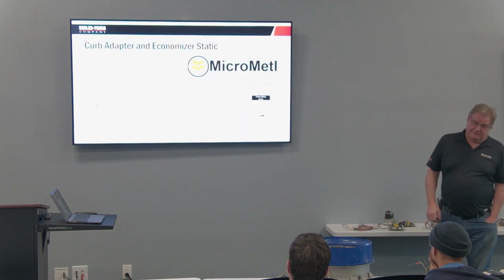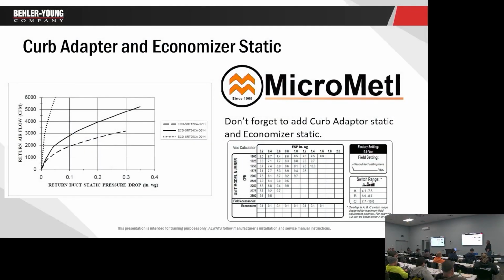The economizer. Okay, if I look at the economizer paperwork, there will be static on there for the economizer. Now, if you look on this tag right here, they're already adding in for the economizer for you. So they're telling you on this unit, just add 0.1 for the economizer. So 0.9 that I figured in the duct plus 0.1 for the economizer. But it should be in the paperwork for the economizer.